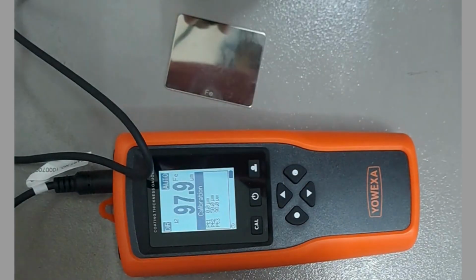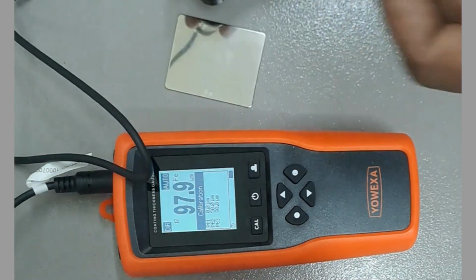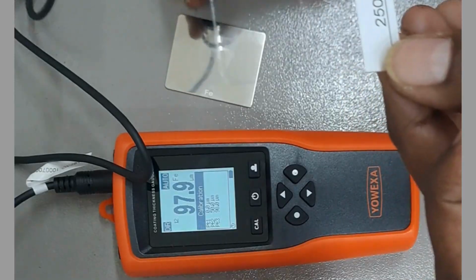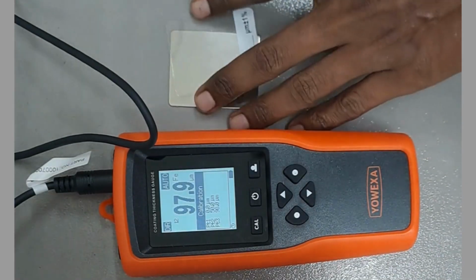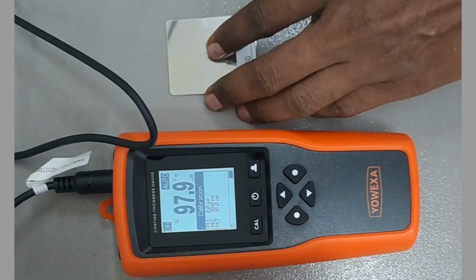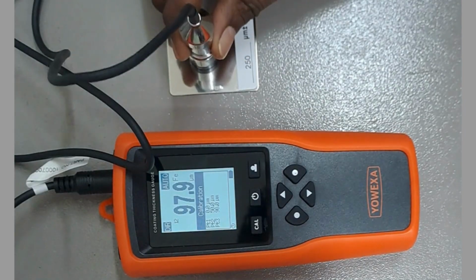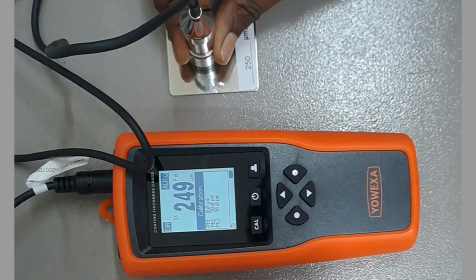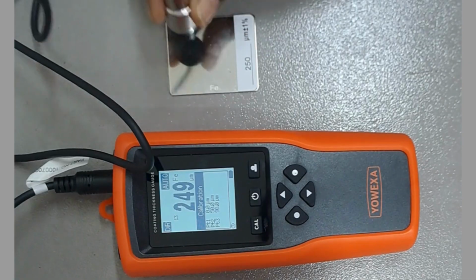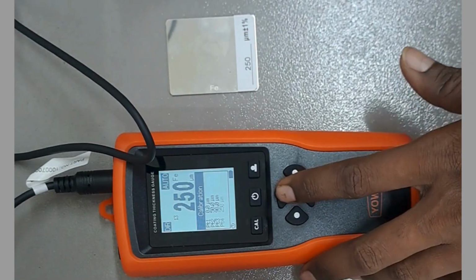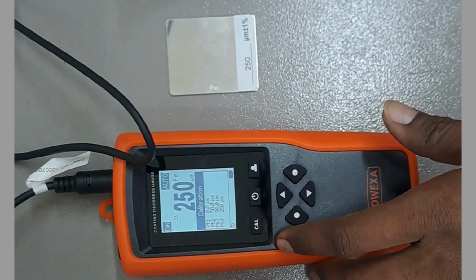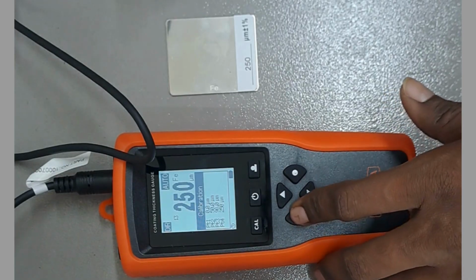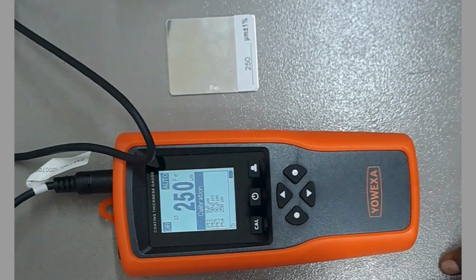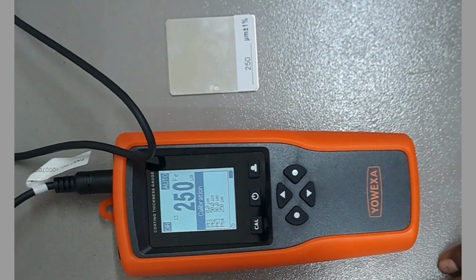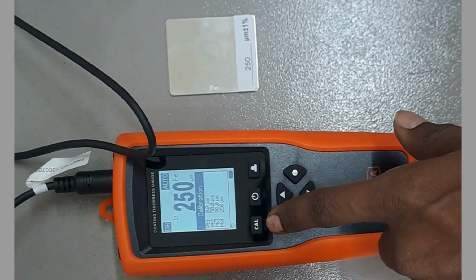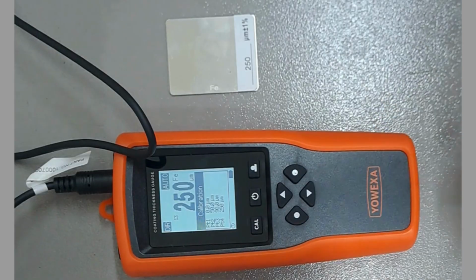And now we will do the fourth point calibration. We will take 250 micron foil, keep it in the base plate, place the probe once, it's 249, so adjust it to 250 and then press the left button to confirm. So now the calibration is over. To exit the calibration mode, press this cal button once.